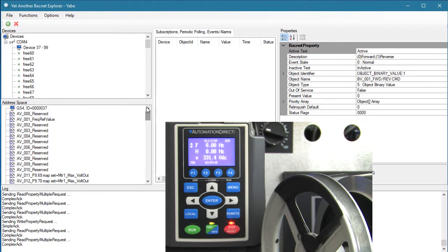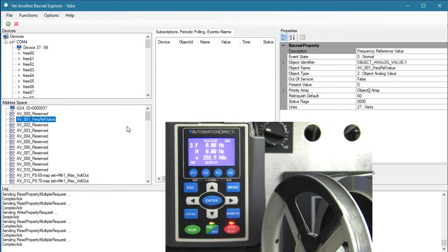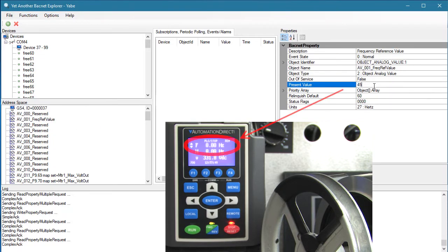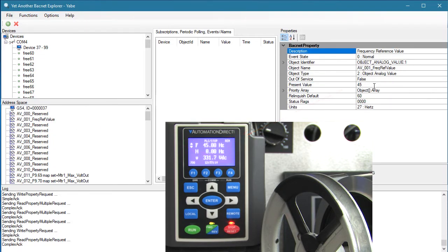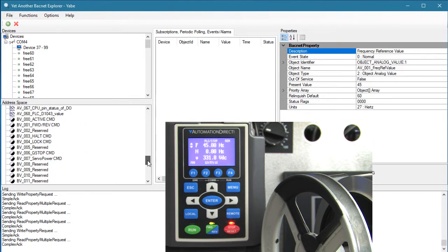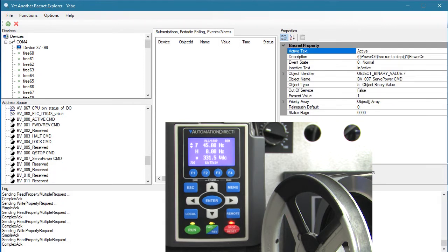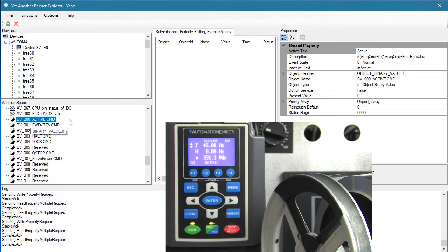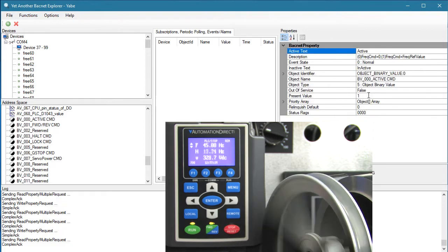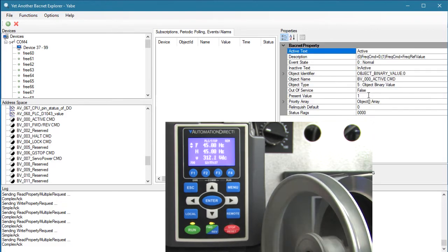Analog value 1 sets the drive's frequency. Let's change that to 45 Hz. Binary value 7 enables the drive, so we'll set that to a 1. Binary value 0 is the run command, and sure enough the drive ramps up to speed.